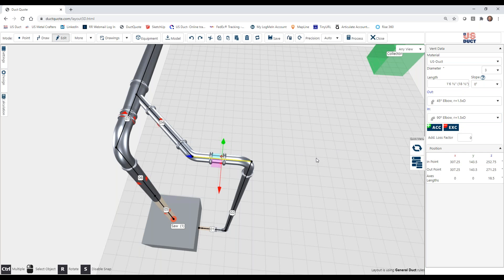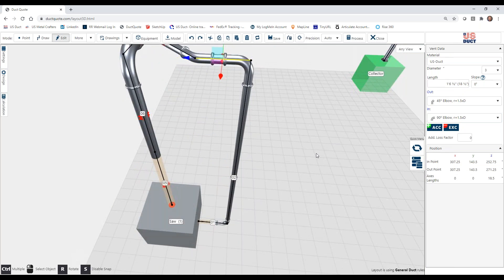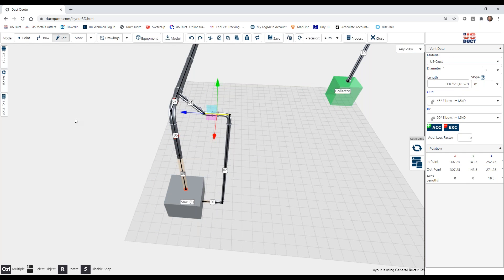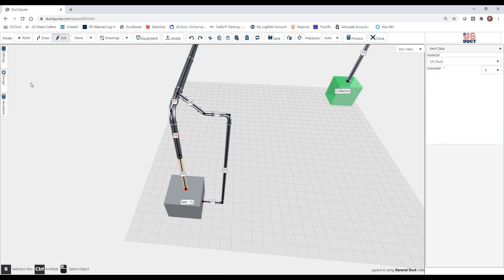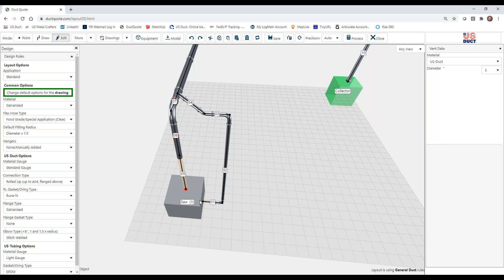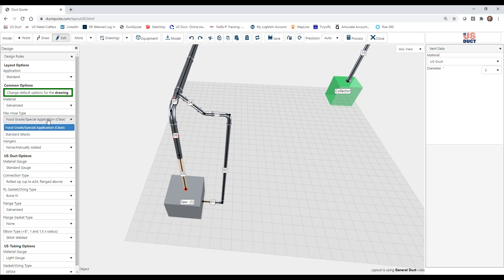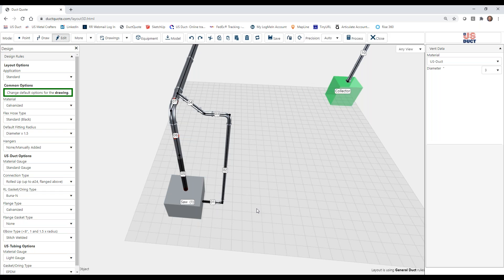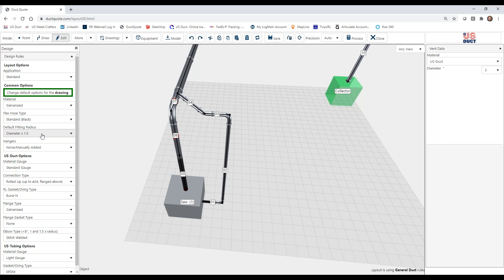Now, the other way that we can change things is we can change things in the design tab. So for instance, we have flex hose on two of these. Currently, it's set to clear. If we change that to black, you can see that we get changes there too. Now, some of these changes in design will affect everything in the drawing. Others will only affect things to be drawn in the future. For instance, if we choose a different radius after we've drawn a bunch of elbows, the current elbows will not be changed. Only those that are drawn after you make the selection.